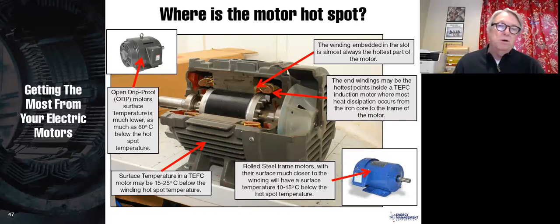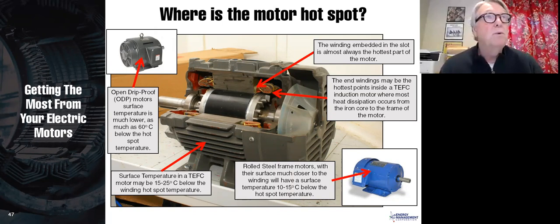Now, the other thing you want to try to measure is your bearing temperature, because the motor may be running at a reasonable rate, but the bearings may be running hot. So you want to try to get those basically on this bearing frame. And we haven't talked about bearing temperatures yet, but we will when we get to our bearing portion of this class.